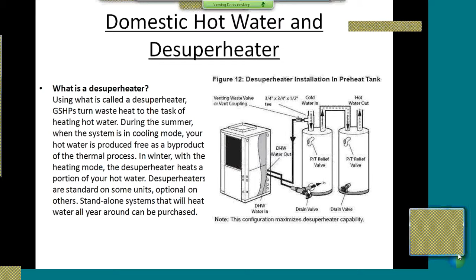With WaterFurnace, the desuperheater is an option. It does not come standard. The picture on the right shows a little bit about the desuperheater. It shows two tanks. The tank on the right would be your primary water heater. The tank on the left would be your preheat tank for the desuperheater. Anytime your heat pump is on, there's a pump here, and this pump will actually flow water out through these lines back into this tank. So that's the desuperheater circuit there.